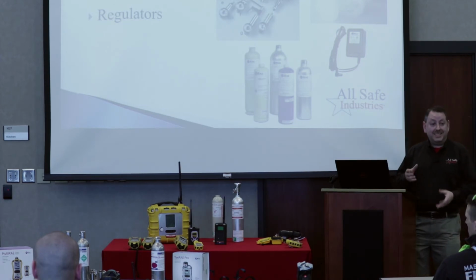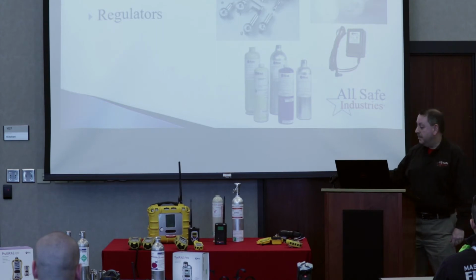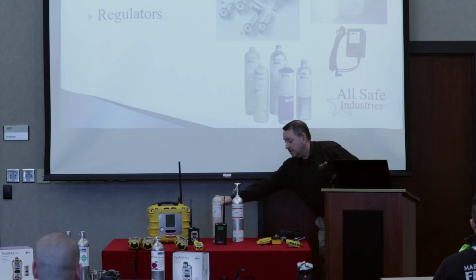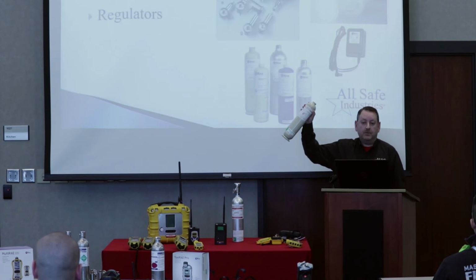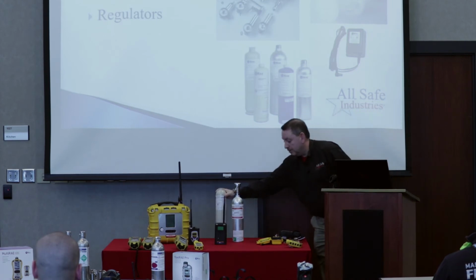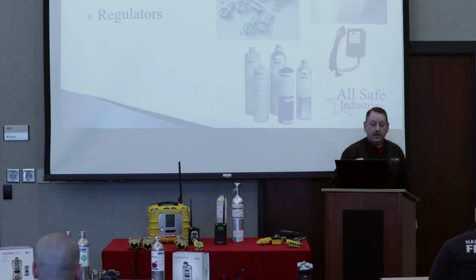So if it's just a single gas meter, you just need the single cylinder of gas. If it's your basic O2, LEL, CO, and H2S, we can mix all 4 of those gases together, so they're all in one cylinder. And then the isobutylene gas is the other gas that would be required for your PID sensor. So we're going to talk about that in more detail as well.